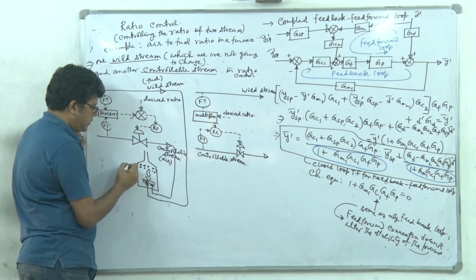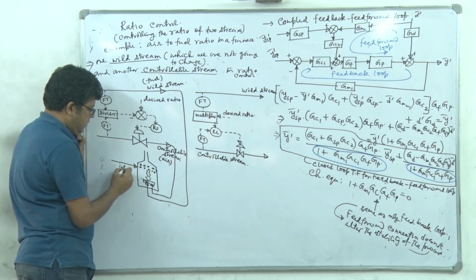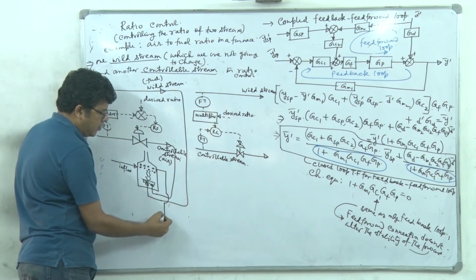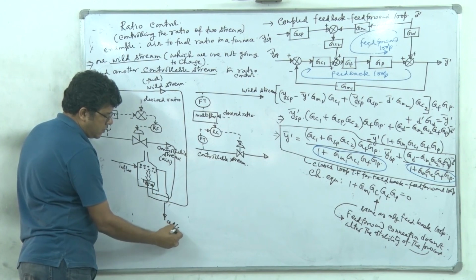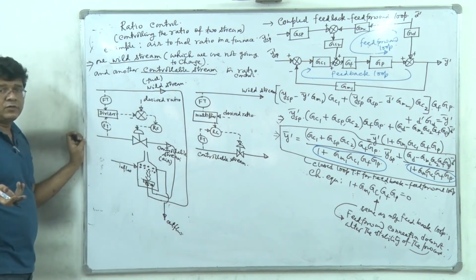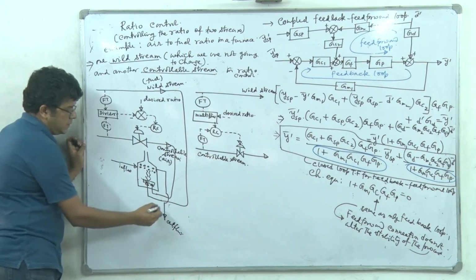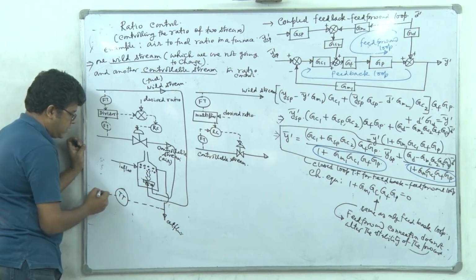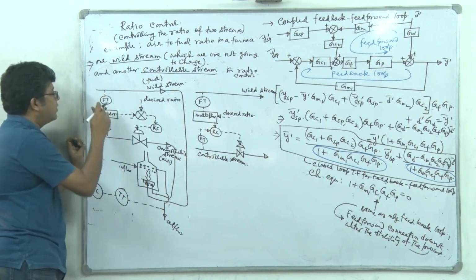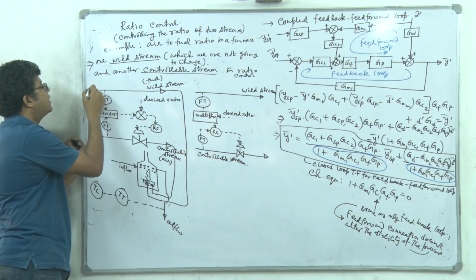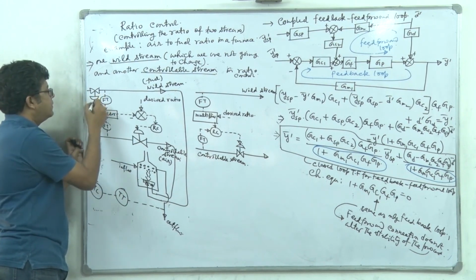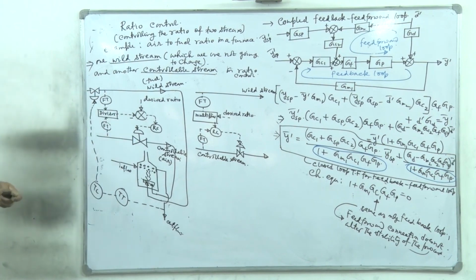This is the inflow, and this, let's say, is the outflow, and I want to control the temperature of this outflow line. So here I will fix a temperature transmitter, then a temperature controller, which will operate this valve in the fuel line.